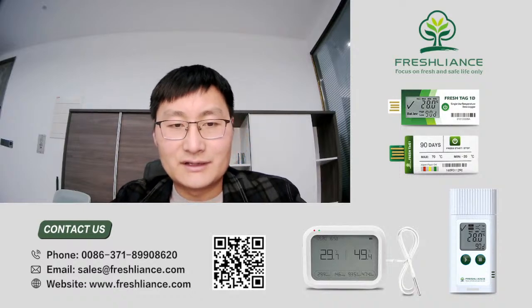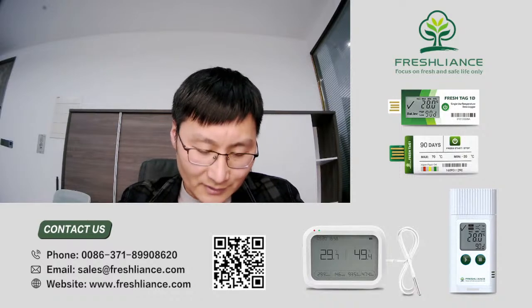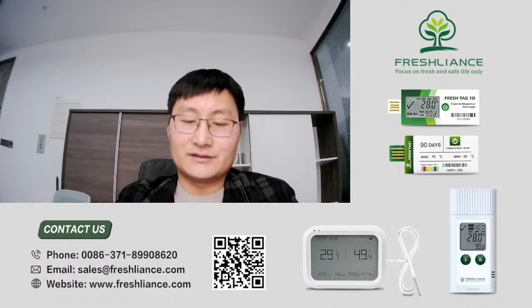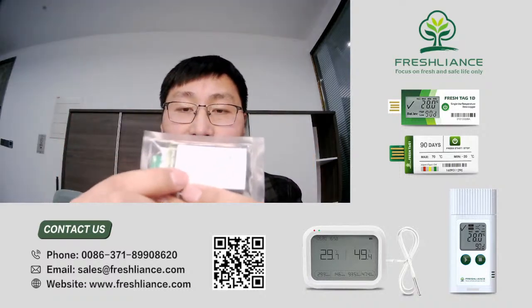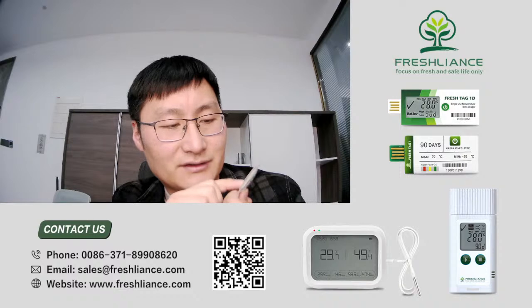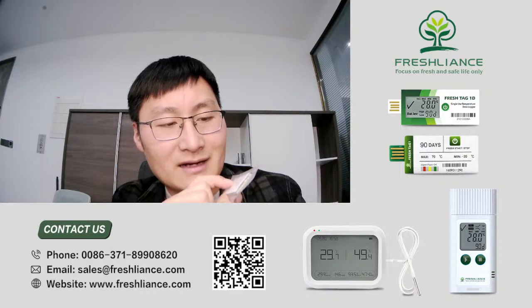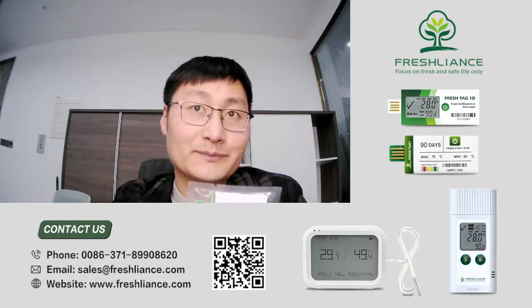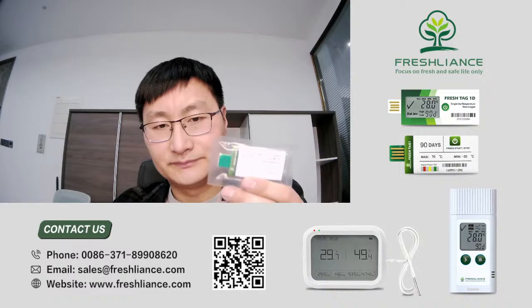Alarm point customizable. And you can see for this unit, there is alarm set. This one, low alarm 2 degrees, high alarm 8 degrees. Yes, take a look.